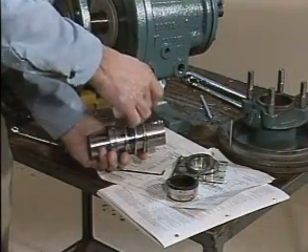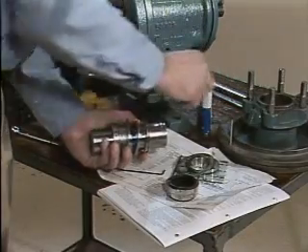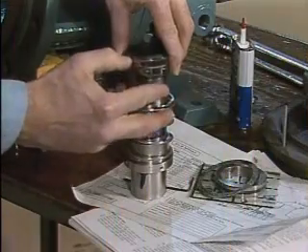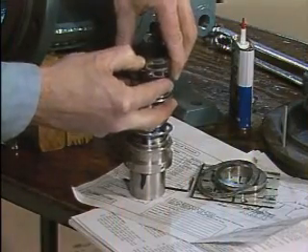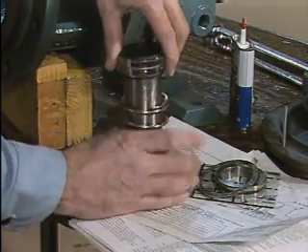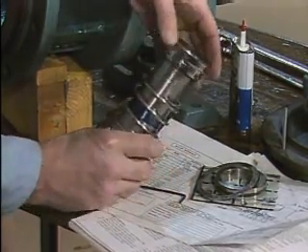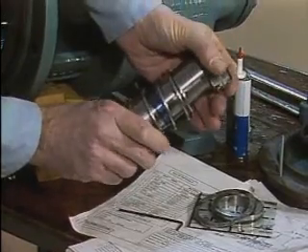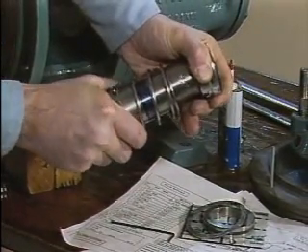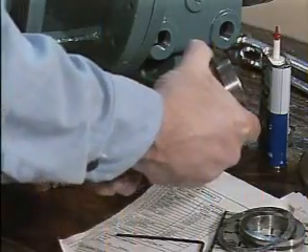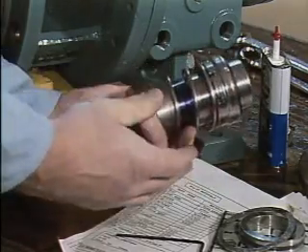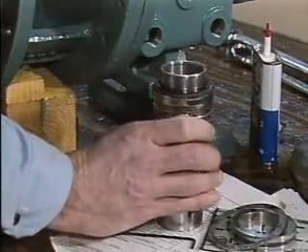Then a small amount of an approved lubricant is applied to the outside of the sleeve, and the rotating ring is installed. As the rotating ring is placed onto the sleeve, the elastomer bellows makes contact with the lubricant and a bonding action occurs between the bellows and the sleeve. The rotating ring must be properly positioned against the spring as quickly as possible.